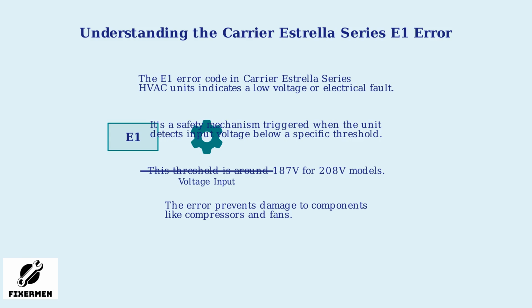The E1 error code in Carrier Estrella series HVAC units indicates a low voltage or electrical fault. It's a safety mechanism triggered when the unit detects input voltage below a specific threshold, around 187 volts for 208-volt models. This error prevents damage to components like compressors and fans.